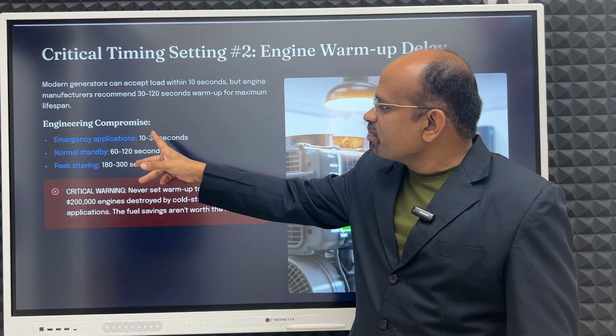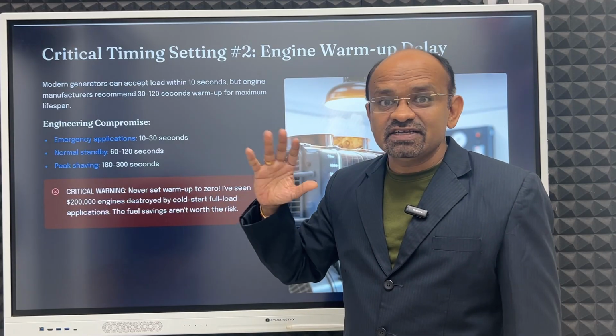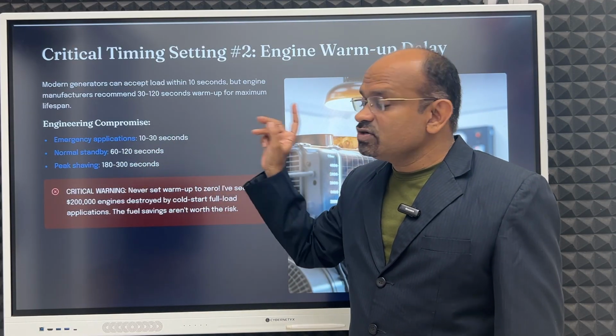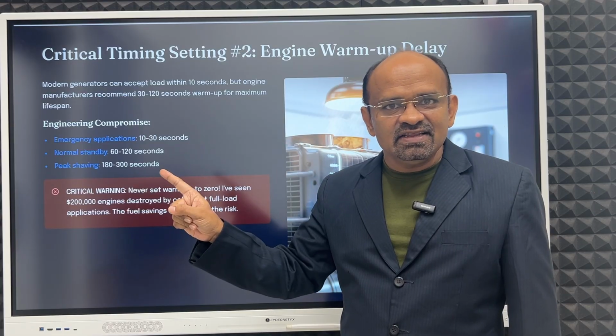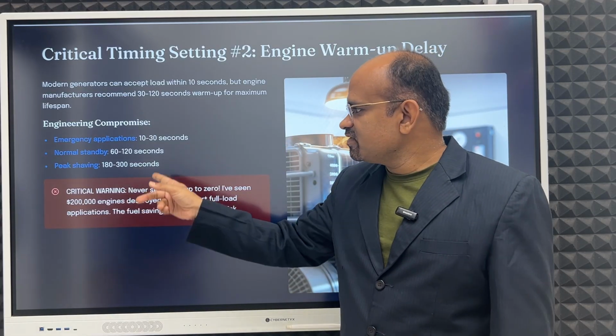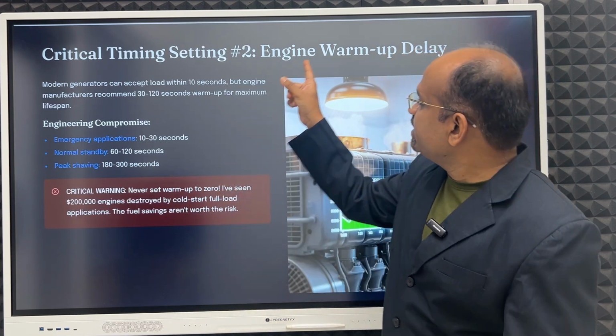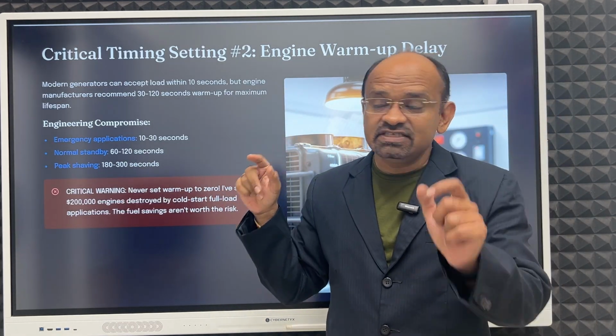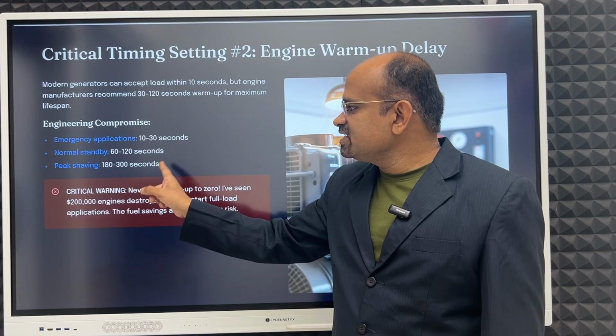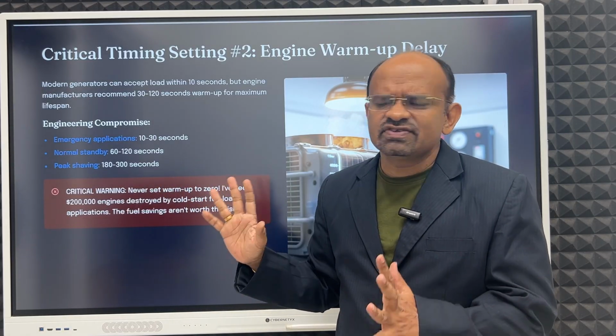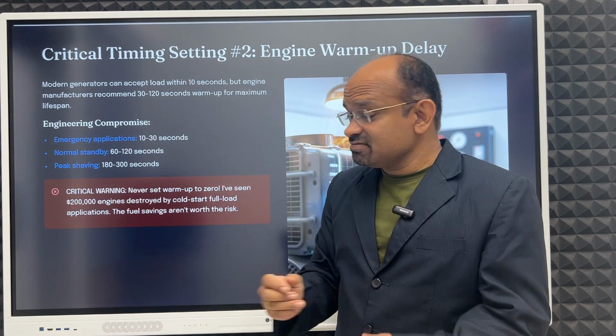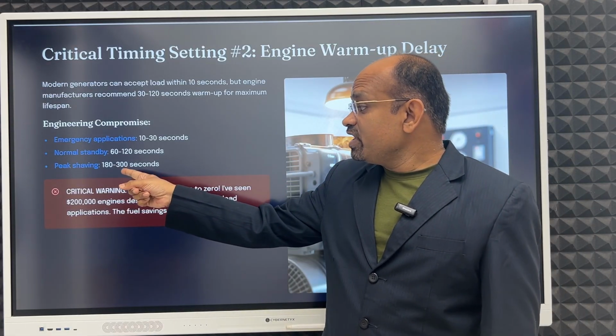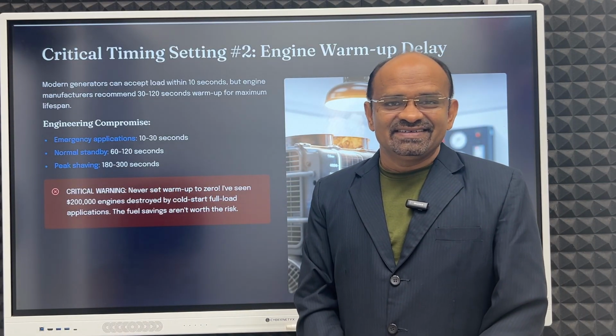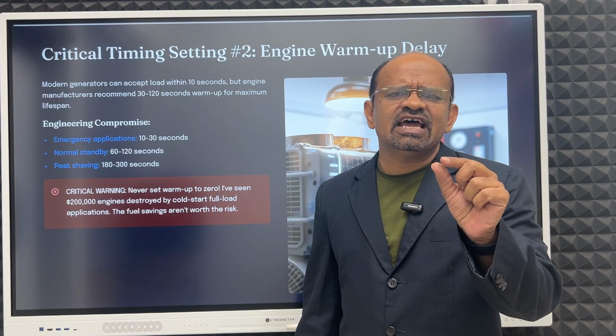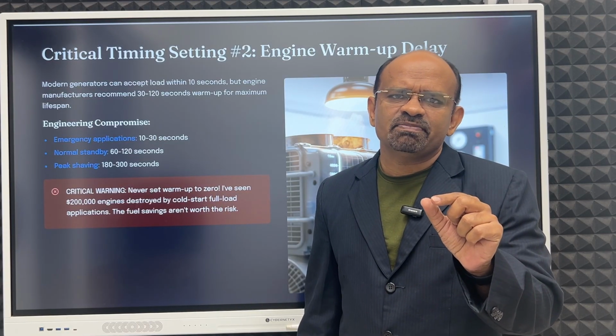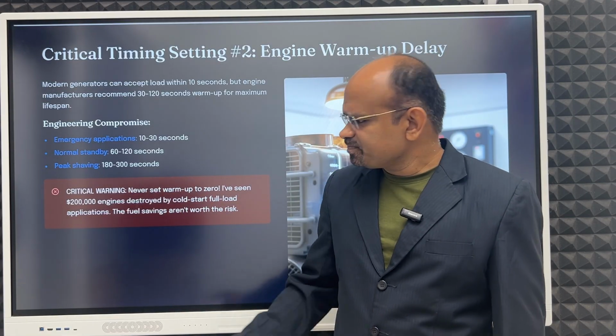Now, the engineering compromise: 10 seconds is the minimum. After that it is good. Emergency applications, 10 to 30 seconds. Medical, hospitals and data centers we have seen. For that, emergency 10 to 30 second warm up delay for the engine. Then normal standby, 60 to 120 seconds for buildings and industry. Then peak shaving we have seen 180 to 300 seconds. If there is a very short outage from utility power supply, then you can use this.